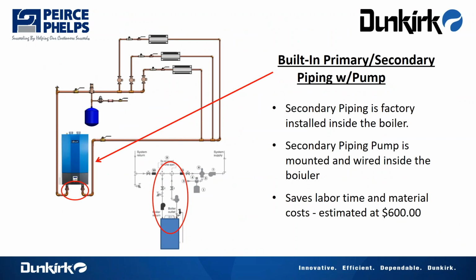This shows the built-in primary secondary aspect, circled on the VLT boiler hooked up to the system. Everything that's going on on that second circle to the right is going on inside our boiler. Any other modulating condensing boiler, that componentry and that near boiler piping has to be hooked into the main system. So the VLT is coming with that, and when you price this boiler, we're there. So again, there's a lot of value in this boiler.